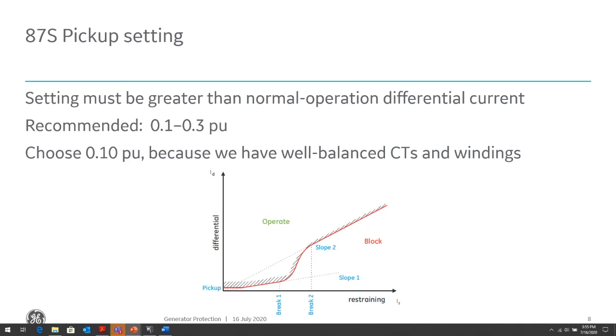Then the other conditions, for example, if you're protecting a transformer with differential, you might have different winding taps, which can cause inaccuracy. So you want to set the minimum pickup a margin above any type of inaccuracies that will cause standing differential current to be seen by the relay. I know sometimes you might not be able to calculate these or not know these correctly.